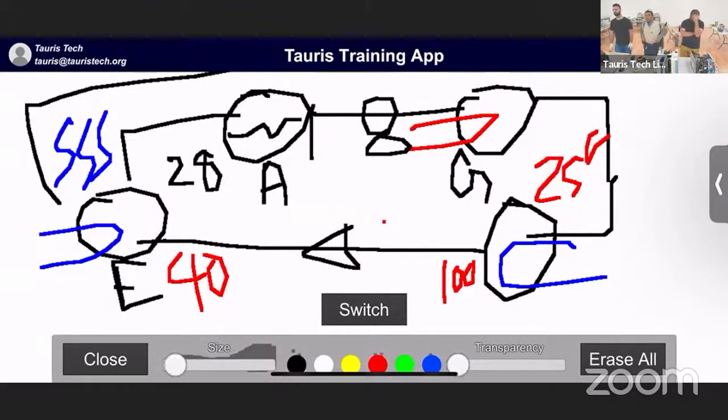So with the purger, right? The reason why we're purging here is not the same reason we're evacuating here. Here we're evacuating because the refrigerant is not going to play well with air and water. Here we need to remove the air because of the pressures. Remember, we're seeing inches of mercury. So that's a deep vacuum. So if I'm sucking in air, I'm not maintaining that deep vacuum.